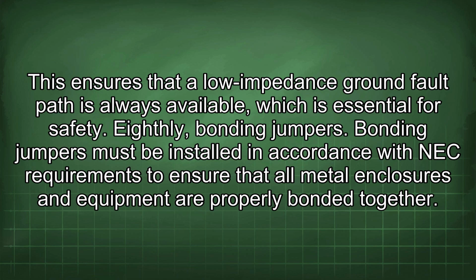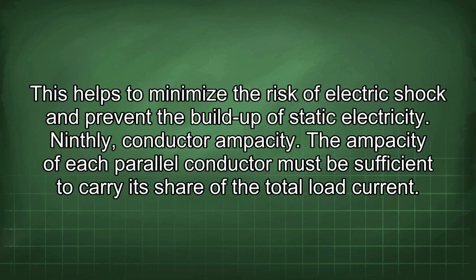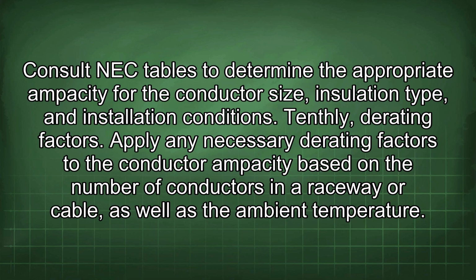Eighthly, bonding jumpers. Bonding jumpers must be installed in accordance with NEC requirements to ensure that all metal enclosures and equipment are properly bonded together. This helps to minimize the risk of electric shock and prevent the build-up of static electricity. Ninthly, conductor ampacity. The ampacity of each parallel conductor must be sufficient to carry its share of the total load current. Consult NEC tables to determine the appropriate ampacity for the conductor size, insulation type, and installation conditions.